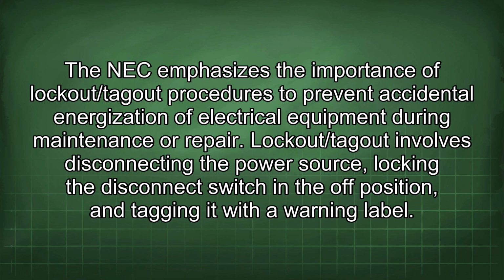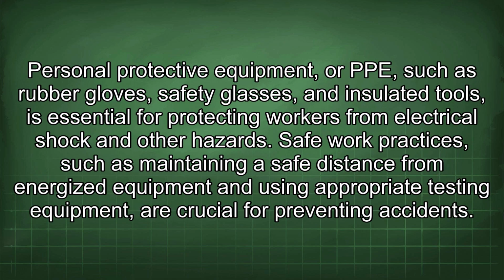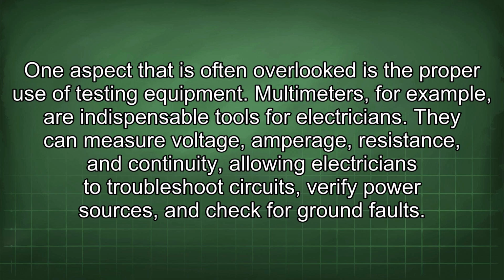Lockout/tagout involves disconnecting the power source, locking the disconnect switch in the off position, and tagging it with a warning label. Personal protective equipment, or PPE, such as rubber gloves, safety glasses, and insulated tools, is essential for protecting workers from electrical shock and other hazards. Safe work practices, such as maintaining a safe distance from energized equipment and using appropriate testing equipment, are crucial for preventing accidents. One aspect that is often overlooked is the proper use of testing equipment.